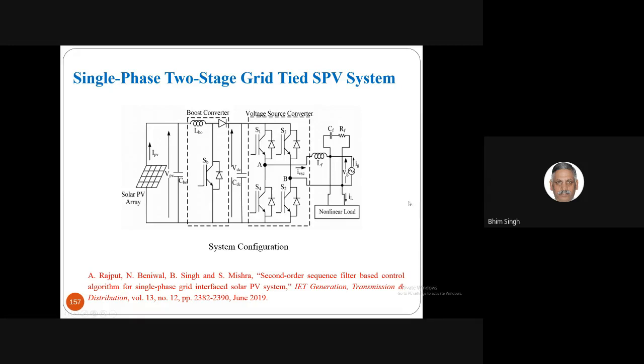And interestingly, now that we have this boost converter, the DC link voltage can be coordinated in relation to the grid. Interestingly, or you can call it unfortunately, our grid voltage varies over a wide range. So if you can have a relation between DC link voltage and the grid, which this system allows, even if you keep, let us say, 340 volt of DC link or 440 volt DC link, solar power can still be fed.